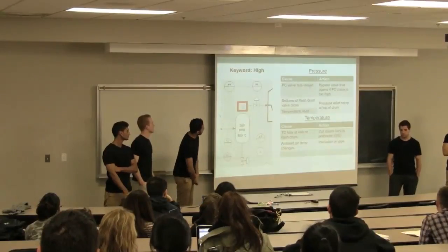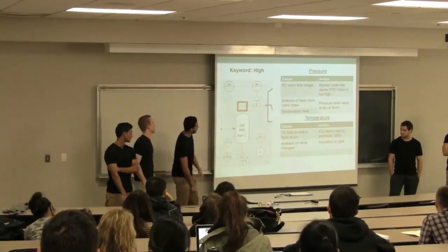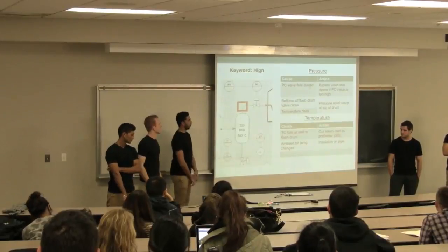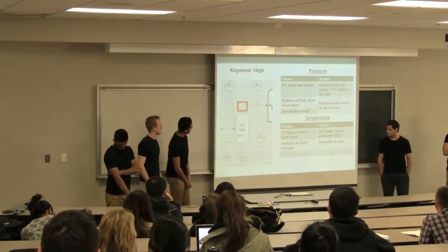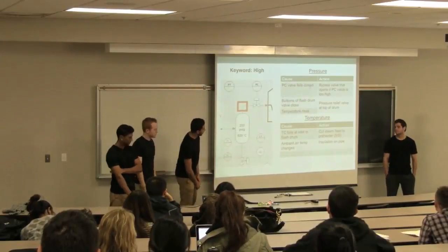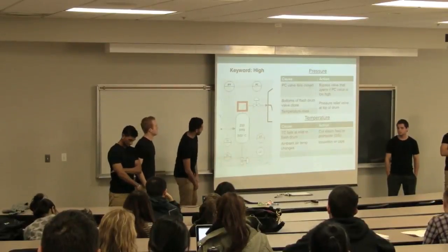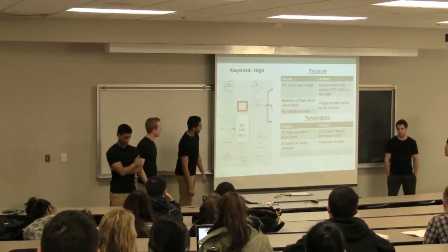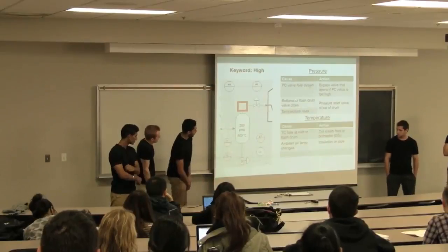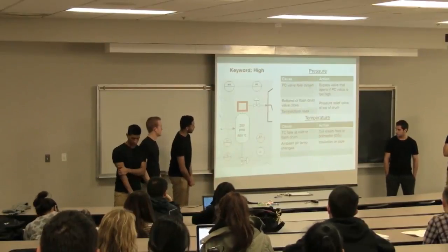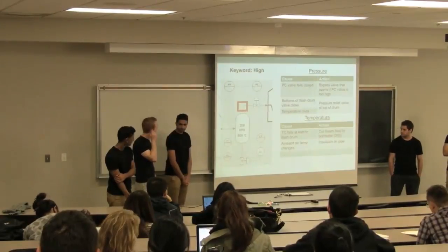If we have the bottoms of the flash drum valve closing and a temperature rise in the flash drum, we implemented a pressure relief valve on top of the drum, and that would relate to the relief part of one of the four levels of safety. Looking at the temperature parameter, if we had high temperature, one of the causes could be the temperature controller failing at the inlet to the flash drum right here. So what we did is implement an SIS system to cut the steam feed, which is controlled by this valve right here. Like Patrick mentioned, if there are any ambient air temperature changes, we can always insulate the pipes to help mitigate any of that damage. Next slide.